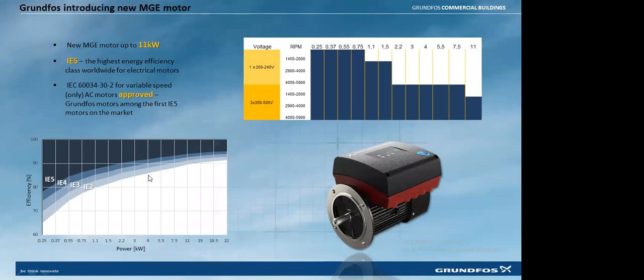So the VFD part is also an integrated part. Whatever output efficiency we declare, that exact output efficiency we will get. Suppose you are using an external VFD, and the motor manufacturer declares some efficiency, say I have an 11 kilowatt motor and they declare 90.2% efficiency. When that motor is connected to an external drive, obviously the drive will have some losses. When the motor runs at partial load, the efficiency of the motor will come down.